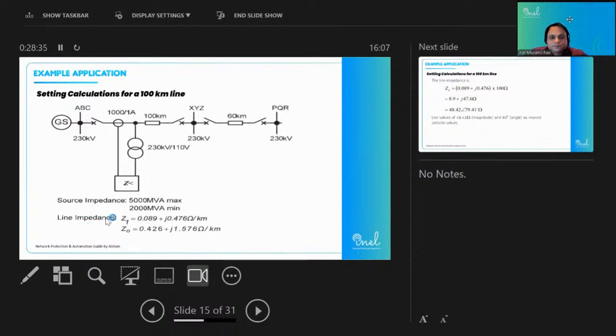Now this is the line impedance. Line impedance is described by R plus jX values. This is Z1, the positive sequence impedance, and its resistance per kilometer is 0.089, and its reactance is 0.476 ohm per kilometer. So if this is per kilometer and the line is 100 kilometers, we need to calculate it for 100 kilometers. So we will multiply this Z1, and also there are the zero sequence values. Normally the zero sequence values are about 3 times the positive sequence values. If the values are not available, then this is a good engineering estimation, so we can consider it. But for now we are using these zero sequence impedance values, 0.426 and 1.576. So this is a typical example. How will we calculate?